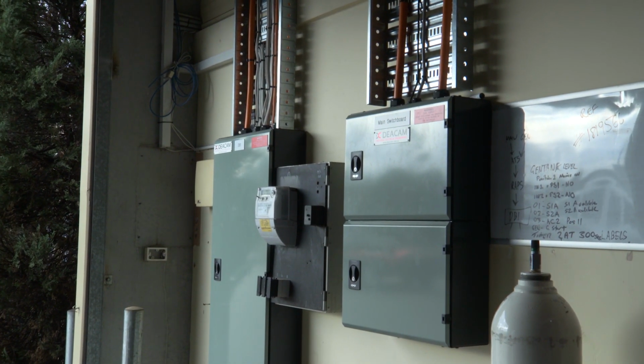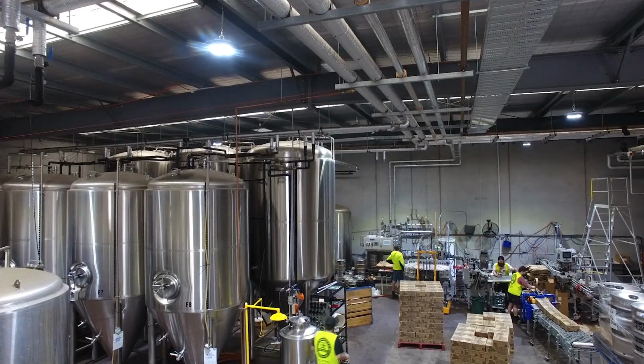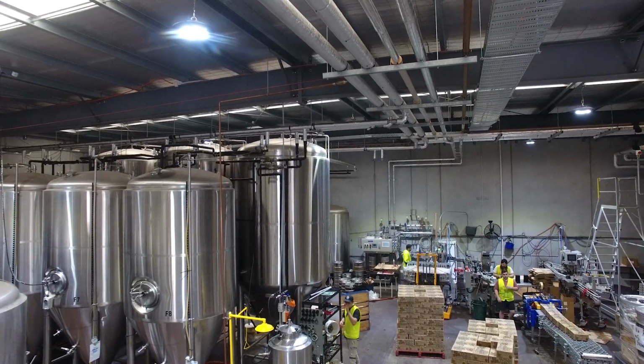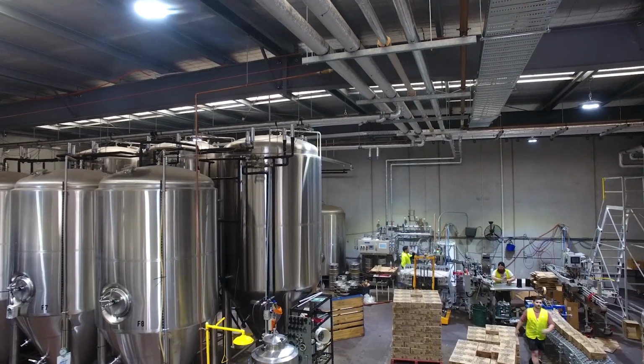And so we have power coming in, not enough, but we also were feeding it incorrectly down the wire as well. Our glycol system, which controls all the tanks, they have 2 compressors and they have 2 pumps. They only need 1 through winter, but when it needs more, the second pump comes on, the second compressor comes on. So rather than being at 46, 50 amps, it got to about 83 amps. Well, that's our load to our site.